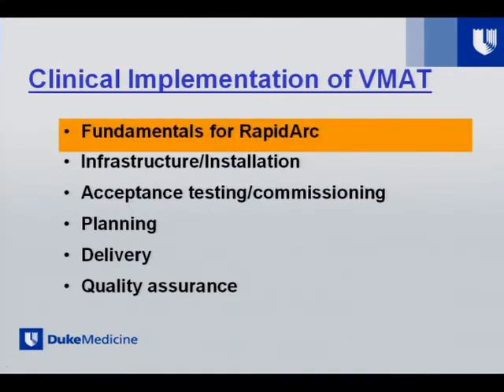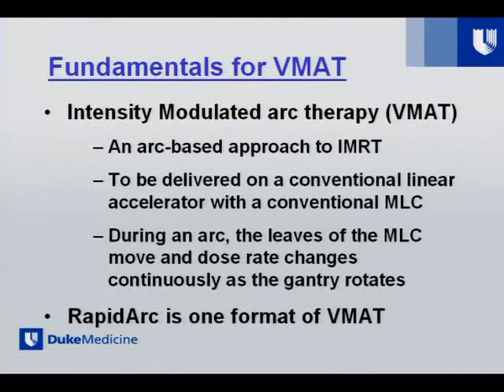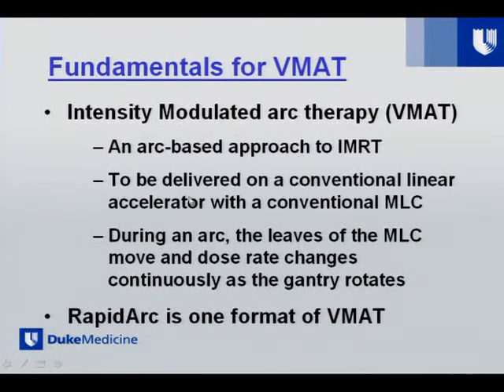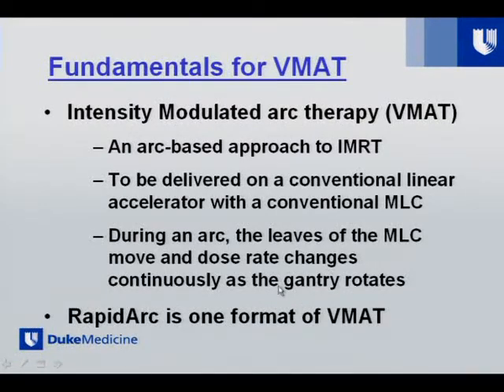First, I'm going to discuss the fundamentals of RapidArc. VMAT — volumetric modulated arc therapy — is an arc-based approach to deliver IMRT, delivered on a conventional linear accelerator with a conventional MLC. During an arc, the leaves of the MLC move and the dose rate changes continuously as the gantry rotates at varying speeds. RapidArc is part of the VMAT format, and VMAT will be used as the standard name going forward.